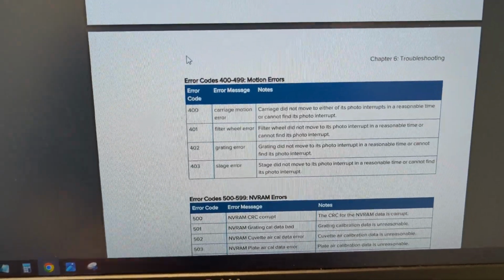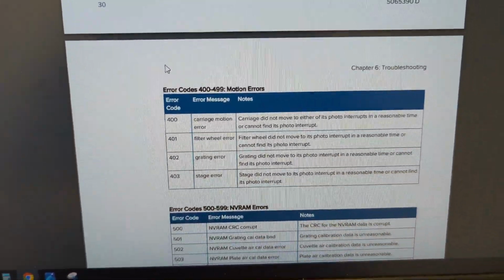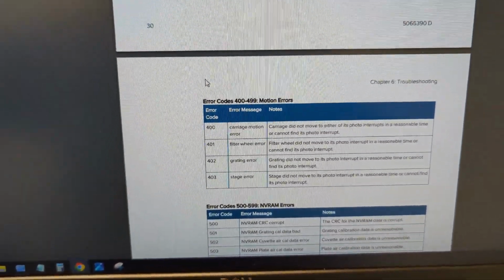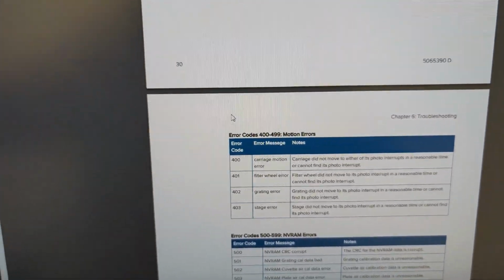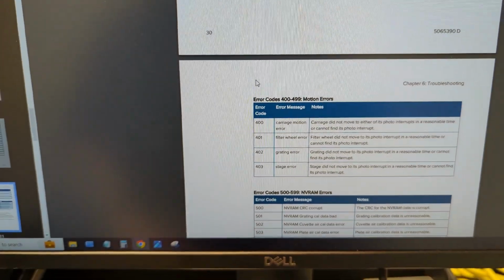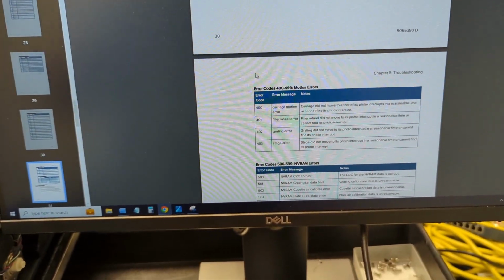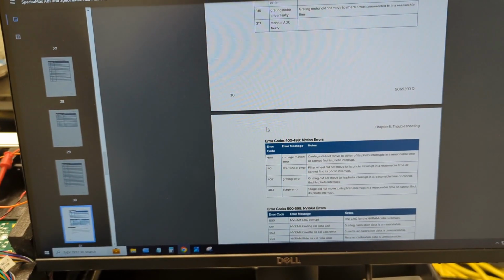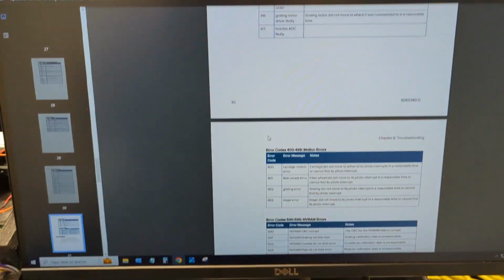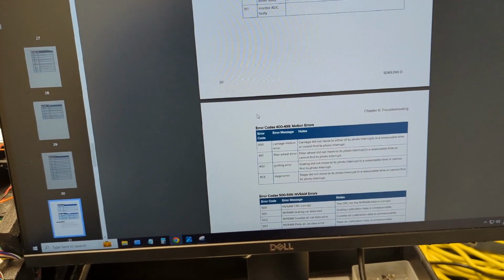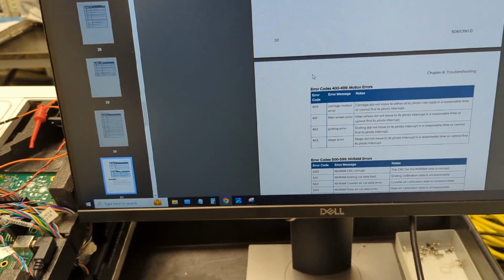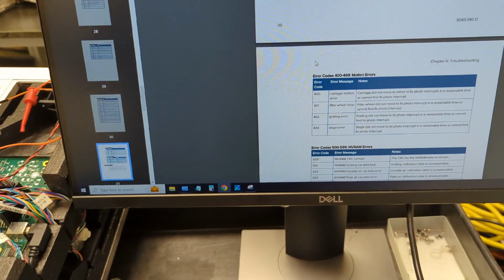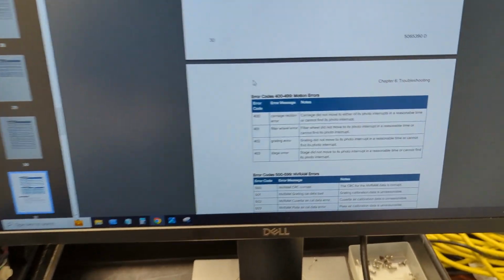You can even see the carriage motion error, photo interrupt, right there. The carriage, again, is the plate carriage, where you put the plate. During startup it will go through a homing procedure so that the unit knows what position the plate is in. And it knows that via these optical homing sensors. They're usually these U-slotted photo micro sensors, where on one end they have a light emitting diode or an infrared emitting diode, and on the other end there's a phototransistor that can sense that light. If an actuator passes through and blocks that light, that's how motors, anything with some sort of motion, usually home themselves. I see these all the time. So that's what this error is saying for the filter wheel.